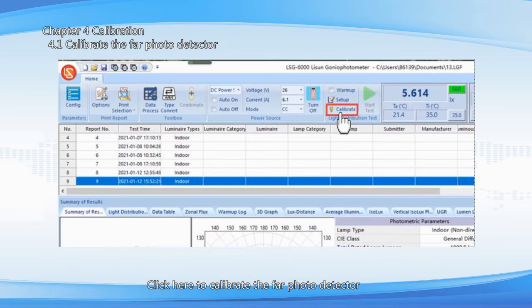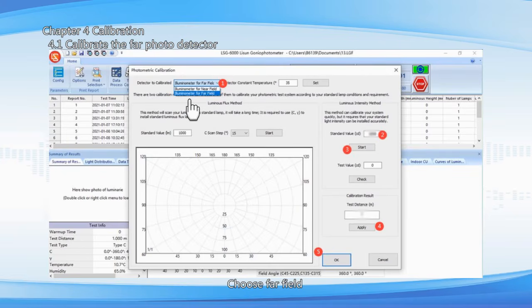Click here to calibrate the far photo detector. Choose far field. We use candela calibration. Input the rated candela according to the certification. Click start. The test distance will change automatically according to your darkroom. Click apply. Click OK.